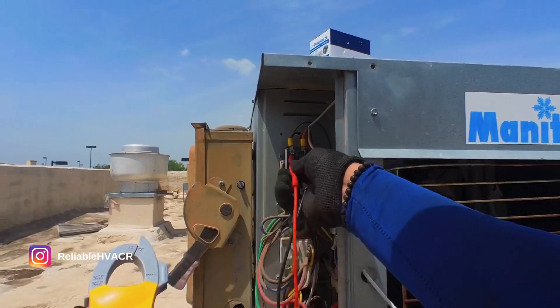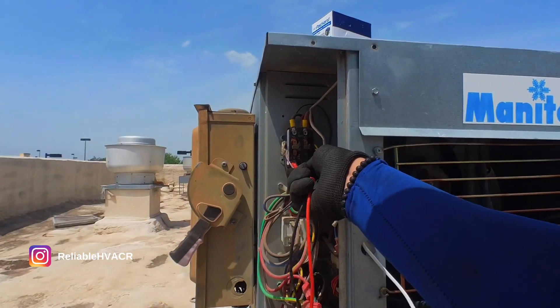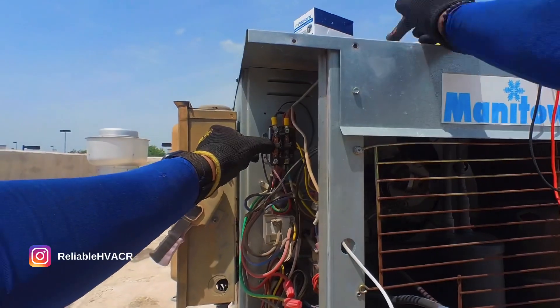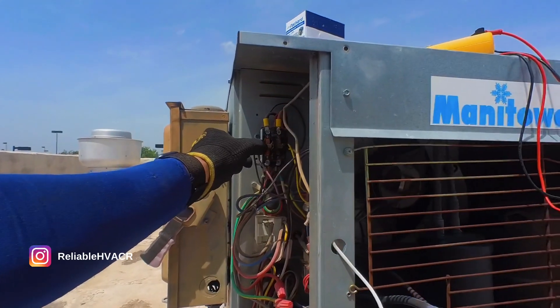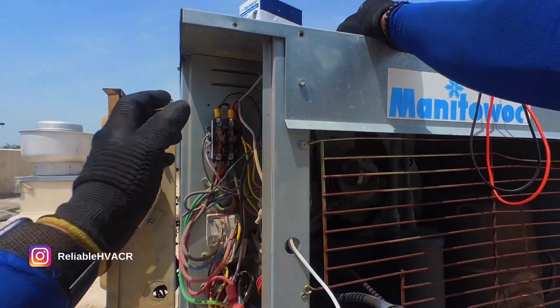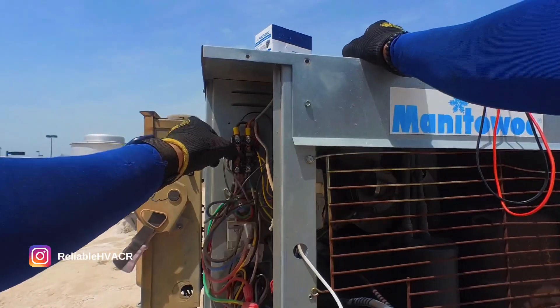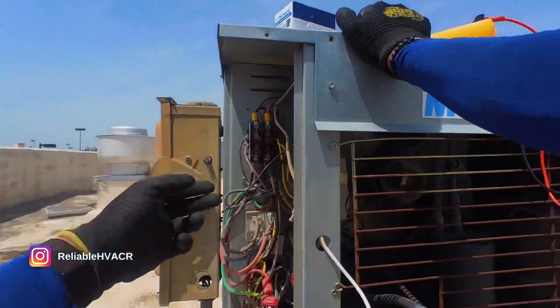I had 209 volts coming in and nothing coming out. The power is off now, but you could tell the contactor was pulled in — but not straight. I came in with my insulated driver and just tapped it and it pulled in. I had checked the coil and I had 24 volts — it's a 24-volt contactor. What's happening is it's every now and then getting stuck. They reset it, it pulls out, straightens itself out, and pulls back in and it works — because the contacts are not bad, not super pitted, but it's just not pulling in right.